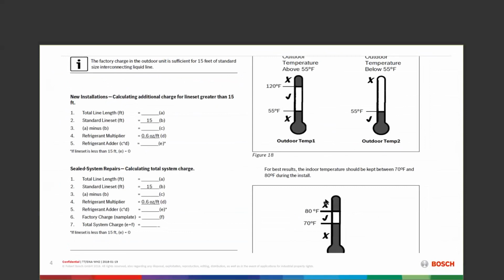We looked at the unit, and you're familiar with the unit. You're looking at 4 wires coming out to the outside unit to make me a heat pump. But we also take a look at how I communicate. I communicate through the refrigeration circuit. I look at a pressure transducer that's inside the machine. But I tell people all the time, we're a very critically charged piece of equipment, and being critically charged, that's how I communicate. So we're looking at number 1, a total length of line set, just to measure that 3/8 liquid line. Give me a linear footage out there. Don't care about elbows or dryers or anything like that. Put that number down. If you're putting the unit in a situation where we are looking at less than 15 foot of line set, leave the refrigerant calculation out.